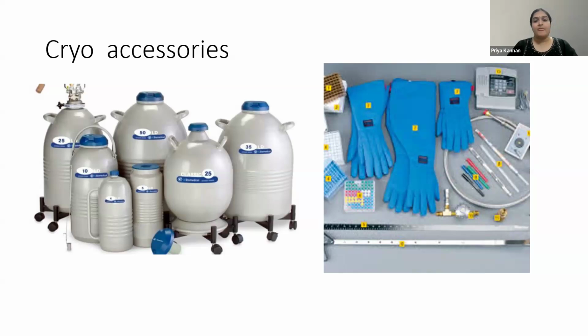So that is important. Even if you're not having a motorized liquid nitrogen dispenser to do your refilling, you can use a thermocol box and a funnel, but you need some safety equipment. You need to have thermogloves. You need to have a scale which can go inside, to check at least once in 3 days the level of the liquid nitrogen in that particular tank. You need to have some tags to put around the cryologs that you're going to use. So these are the things that you definitely need, and goggles.